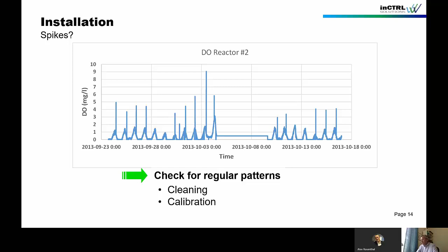The same you could have with calibration, with auto calibration, where you basically also measure the high standard instead of excluding that from the proper database. Same principle: you go into the configuration menu and extend the waiting time a little bit after cleaning or calibration. It might be that actually this is not a problem of the sensor, that it is real. So you have these concentration spikes for whatever reason, and the sensor measures that correctly. And again, you would try to find any schedule matching these spikes. Very often it has to do with pumping schedules.